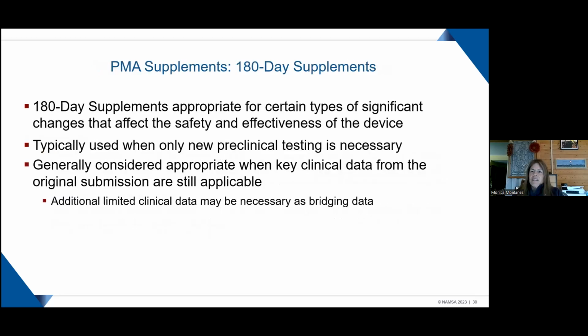So now we're focusing on 180-day supplements, and when are those appropriate? Well, in this particular case, 180 days are appropriate for certain types of significant changes that affect safety and effectiveness of the device. It's typically used only when new preclinical testing is necessary, and it's generally considered appropriate when key clinical data from the original submission is still applicable. So the changes shouldn't impact your clinical study, in other words.